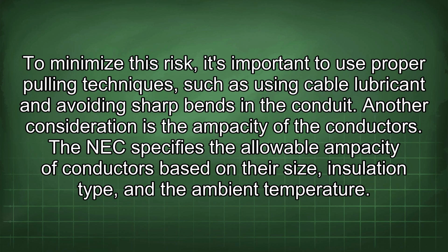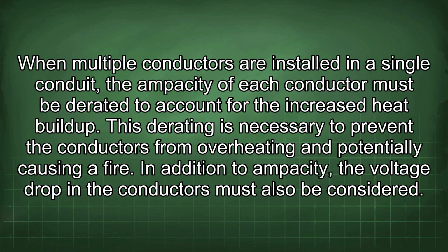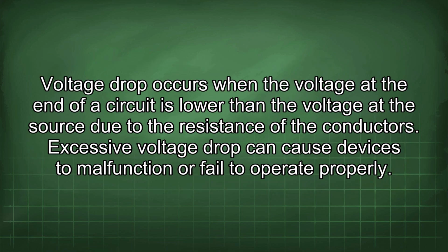The NEC specifies the allowable ampacity of conductors based on their size, insulation type, and the ambient temperature. When multiple conductors are installed in a single conduit, the ampacity of each conductor must be derated to account for the increased heat buildup. This derating is necessary to prevent the conductors from overheating and potentially causing a fire. In addition to ampacity, the voltage drop in the conductors must also be considered. Voltage drop occurs when the voltage at the end of a circuit is lower than the voltage at the source due to the resistance of the conductors. Excessive voltage drop can cause devices to malfunction or fail to operate properly.